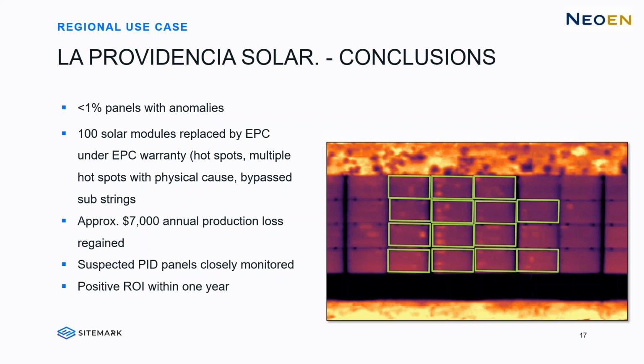Secondly, we also calculated, based on the feed-in tariffs for this particular site, that they were able to increase production by about $7,000 in terms of the losses resulting from the defects, and the suspected PID issues were being closely monitored because some sections on the site had progressive PID.